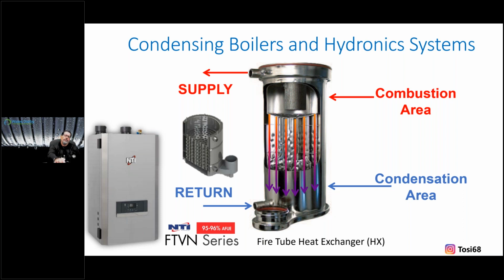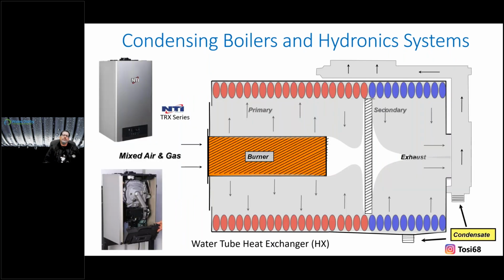And that is going to do one thing, and I'm going to go back a slide here, on the exhaust side, right? What we want to do is reduce the temperature of the exhaust as much as possible. So here it is. If we have no outdoor reset, maybe just going off a high limit, let's say it's 180, man, we have a lot to take out of those products of combustion to even get to the better state, the state of condensing, right? So what we want to do is lower water temperature, have the coolest water at the last stage of our combustion, and now we're extracting all that heat energy, even in the vapor of our combustion. And now we're going to turn it and collapse it into a liquid. And that again is another benefit, and I'll show you that in a little bit.